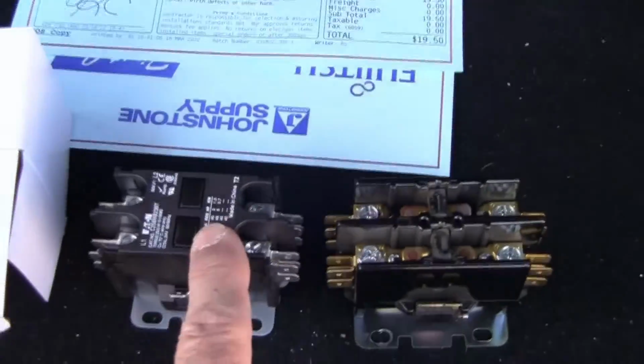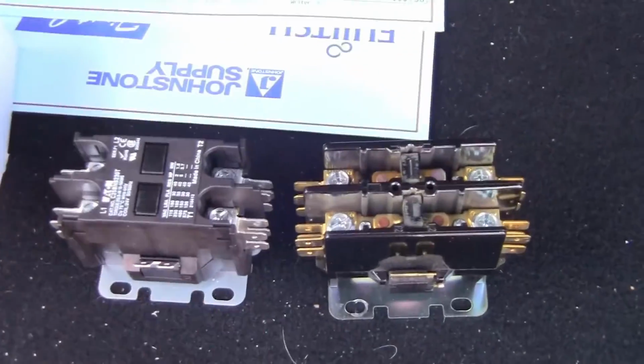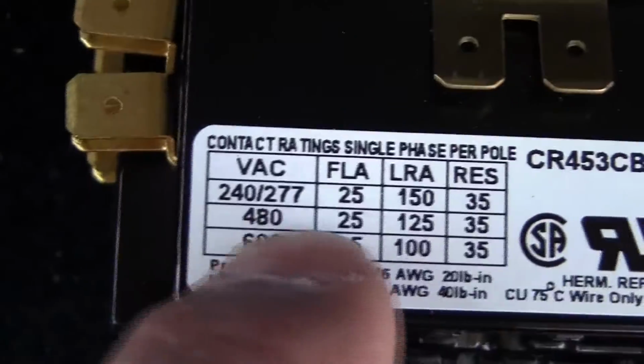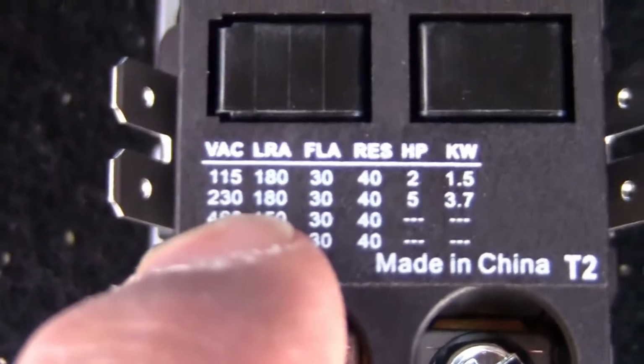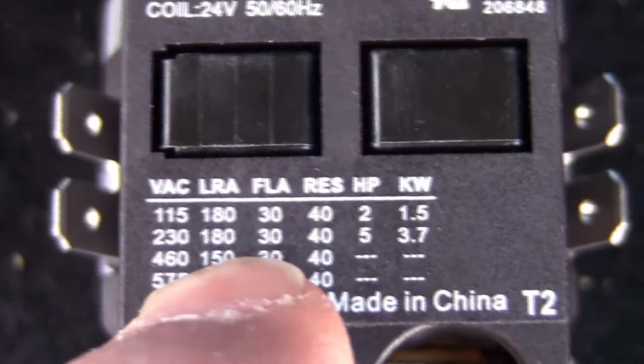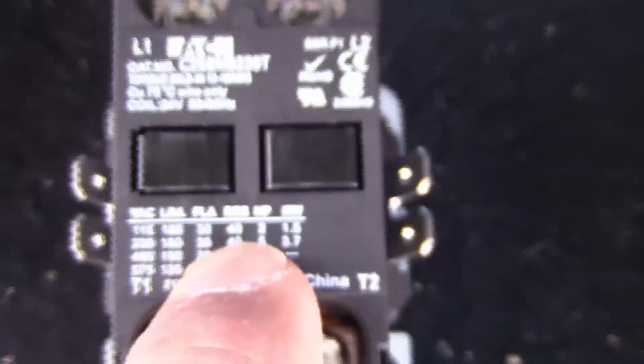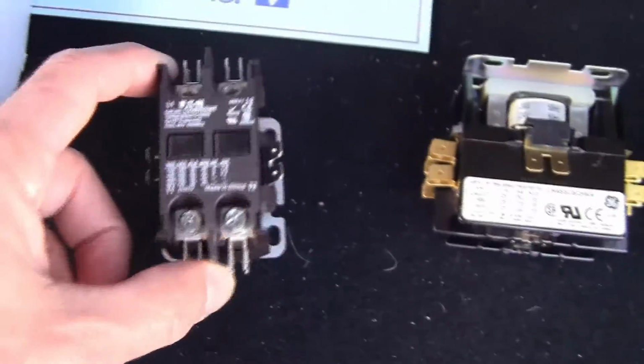Now, when I look at my replacement contactor, of course I want to look at my ratings. Okay, so the 2 ratings that we want to look at are the coil voltage, 24 volts on the new one, and of course the old one here has 24 volts, so that matches up. And then on the pole ratings for the old one, we see here that under 240 volts it's 25 full load amps, and over here at 230 volts the full load amps is 30. These are actually rated 5 amps higher. So this will absolutely satisfy our...